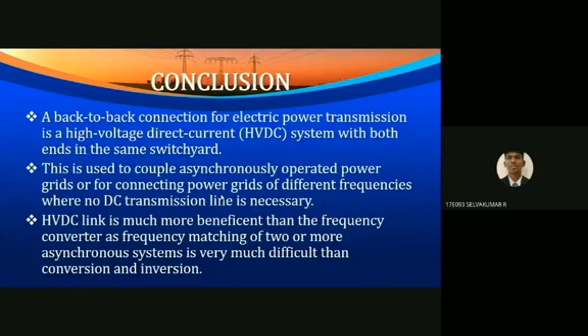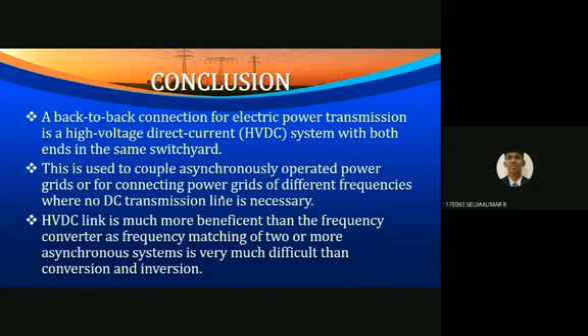In conclusion, the back-to-back connection for electric power transmission is a high voltage direct current system with both ends in the same switchyard. This is used to couple asynchronously operated power grids or for connecting power grids of different frequencies where no DC transmission line is necessary.